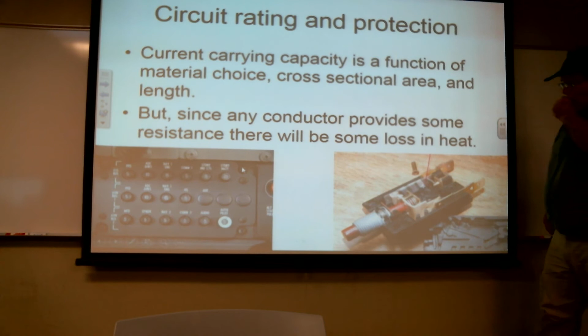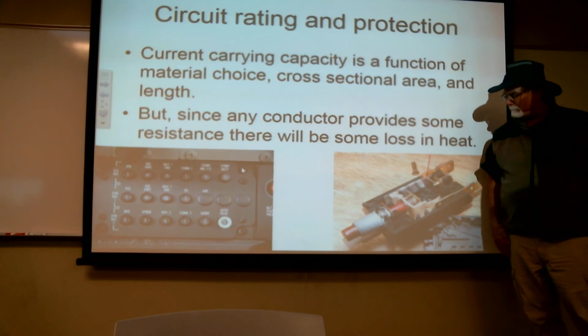Now, circuit breakers somewhat work like fuses do, in that they'll have some type of heating element through which either all or part of the current will travel. And if the current exceeds a certain value, that heating element will get hot enough to cause a bimetallic plate to start flexing. And as it starts flexing, it pops or trips the latch that holds the switch together, causing this to pop back out.